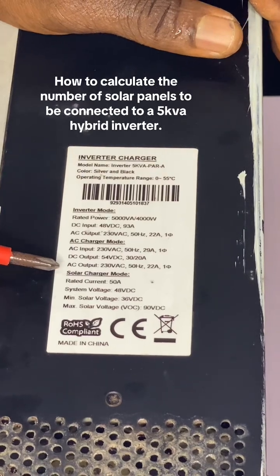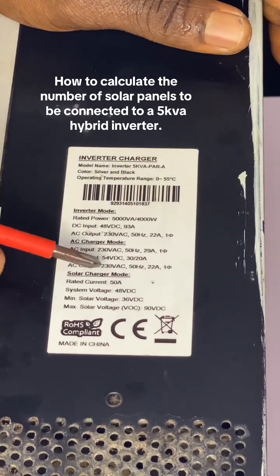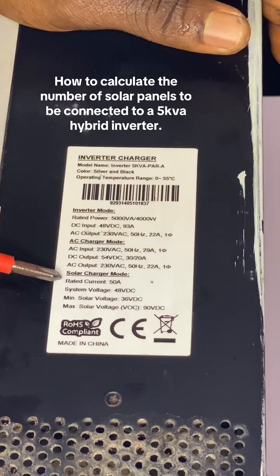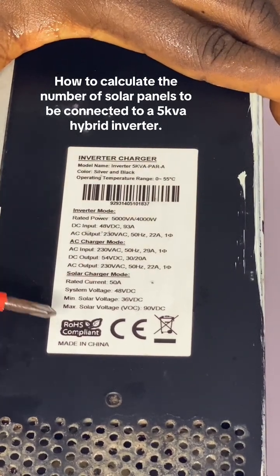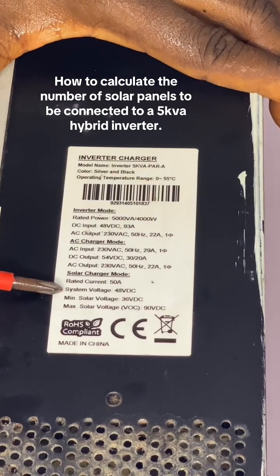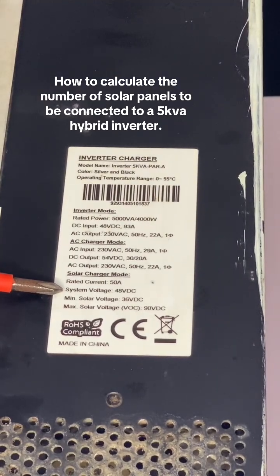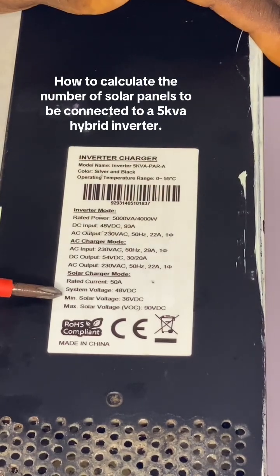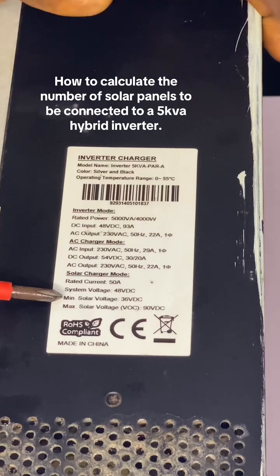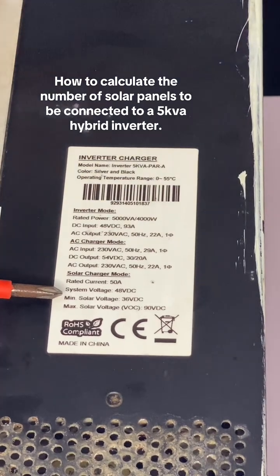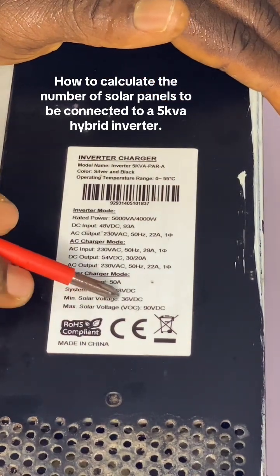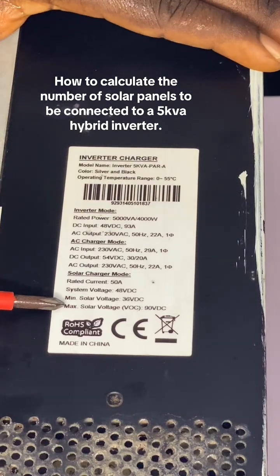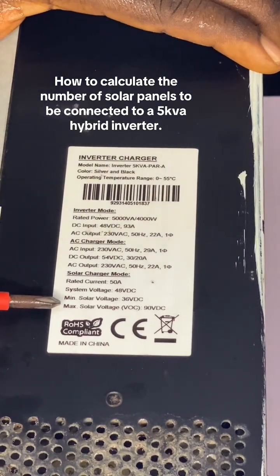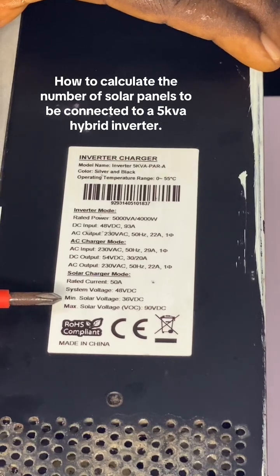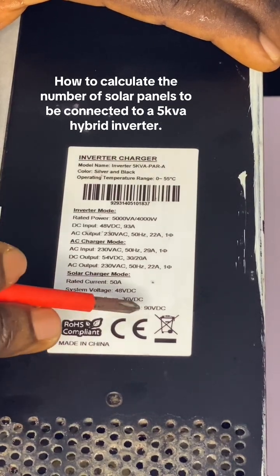When you check the solar part, which is the solar charger mode, the charge controller is 50 amps. Then the system voltage for this inverter is 48 volts. The minimum solar voltage that must be connected to this inverter is 36 volts according to the label. Now the maximum solar voltage, the VOC, is 90 volts.